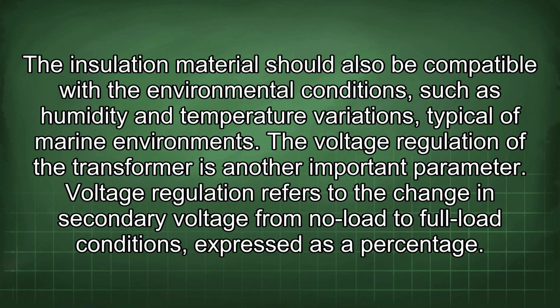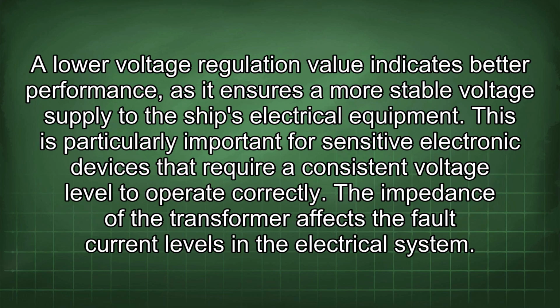The voltage regulation of the transformer is another important parameter. Voltage regulation refers to the change in secondary voltage from no load to full load conditions expressed as a percentage. A lower voltage regulation value indicates better performance, as it ensures a more stable voltage supply to the ship's electrical equipment. This is particularly important for sensitive electronic devices that require a consistent voltage level to operate correctly.